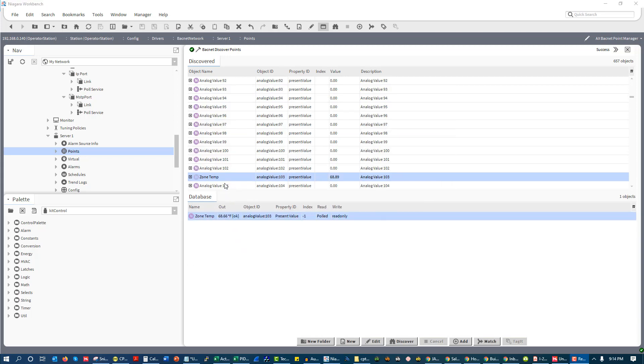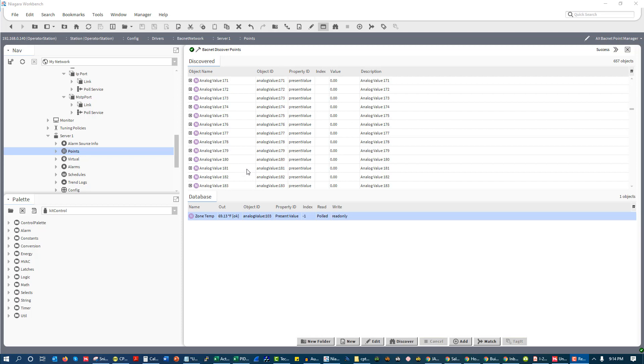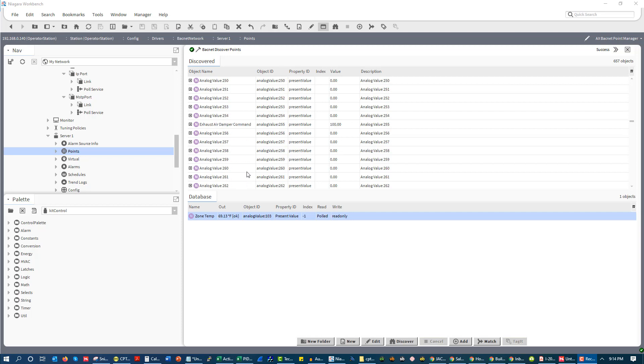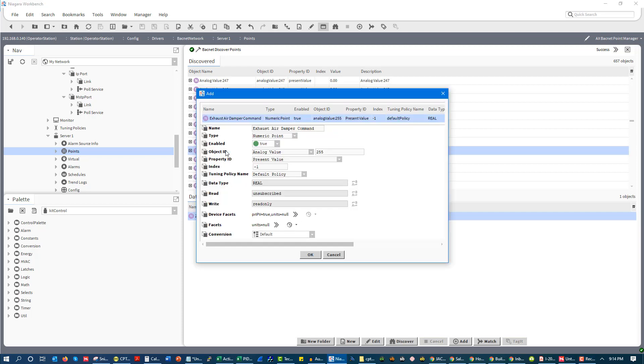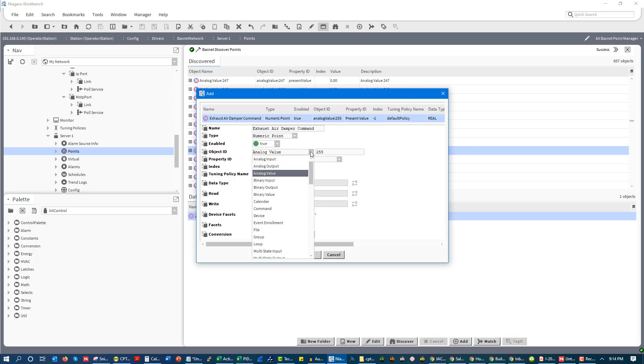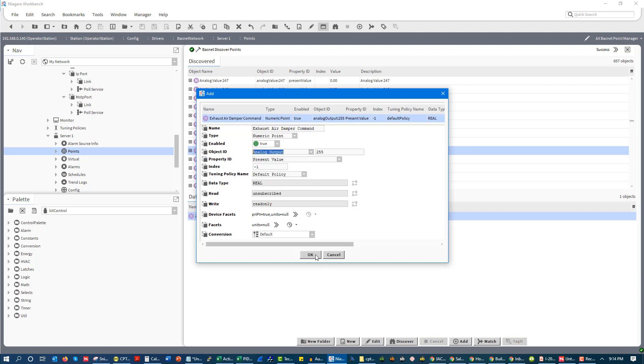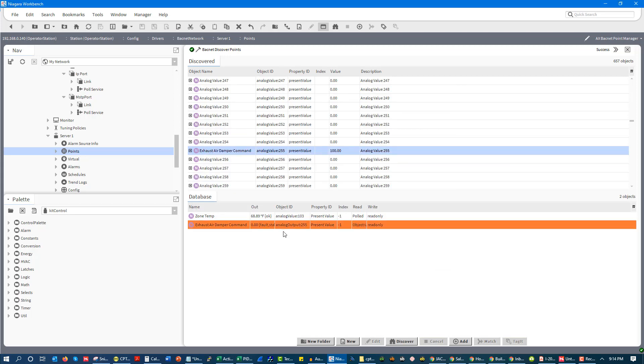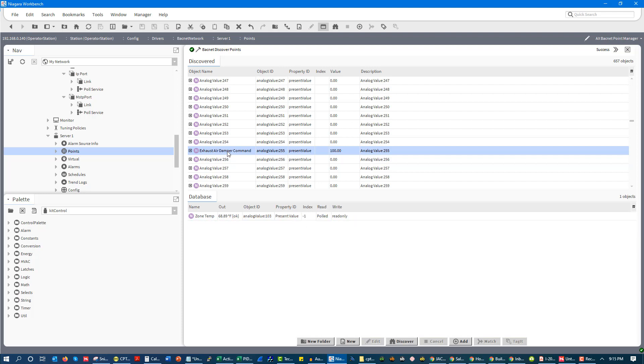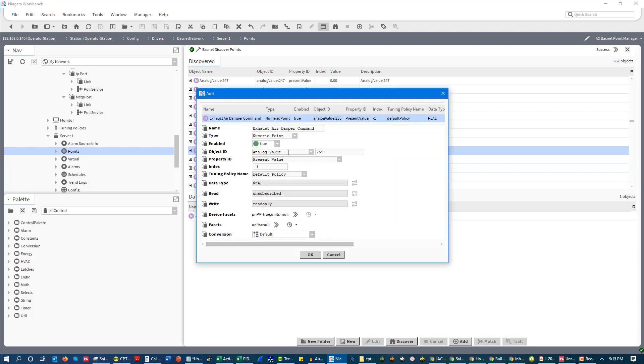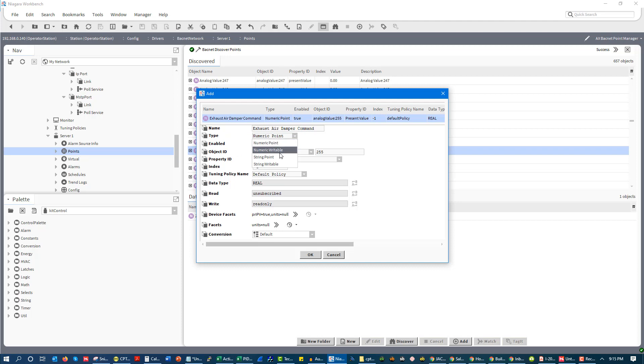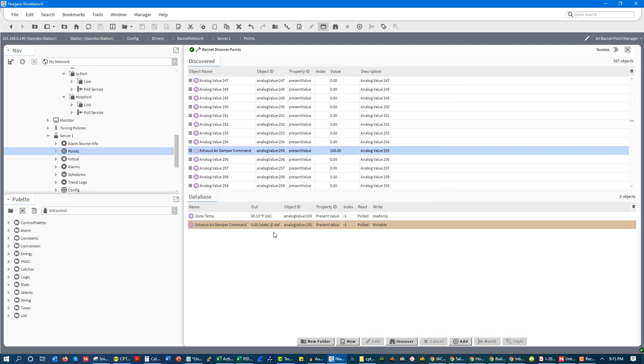Now, at this point, it's important to understand how your manufacturer's software works, because for some folks, this is all you're going to have to do. You're going to map in. It's going to show up as an AI if it's a read only point. It's going to show up as an AV or an AO if it's a writable point with a priority array. Anyway, in the case of this software right here, what we need to do, let's say we want to go and add this exhaust air damper command. And we start looking at it, and we're like, oh man, it's AV, but it's read only. Oh, I know how to fix this. Maybe AV's messed up, so I'll do analog output. And we see immediately we get a fault, because that's not the right object type. But then you say to yourself, like, analog value, that has a priority array, so why am I not able to write to it? Well, real simple, with this software the way it is, you need to pick a writable point. So we'll do that. We'll enable the point, and now it'll be writable, and life is good.